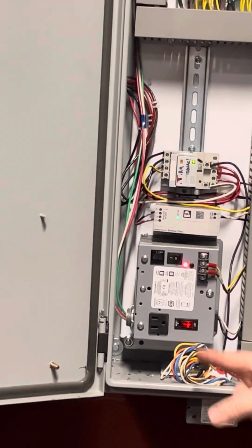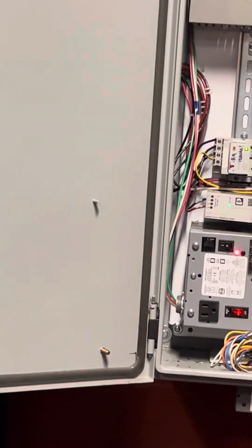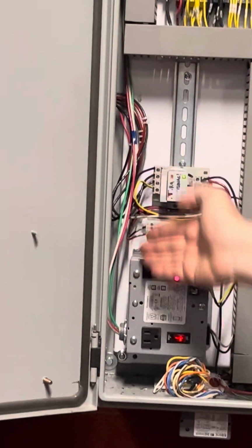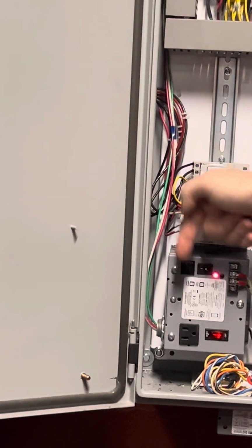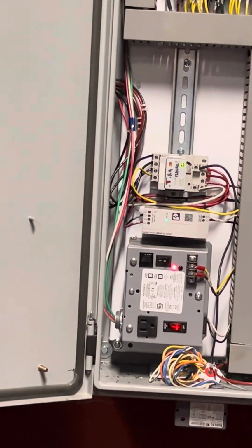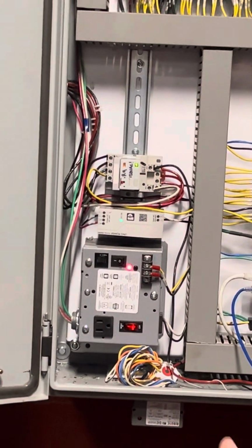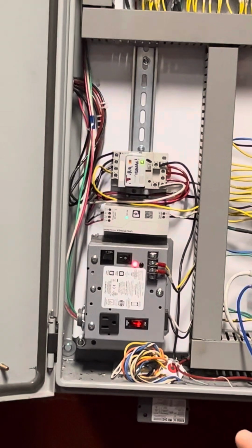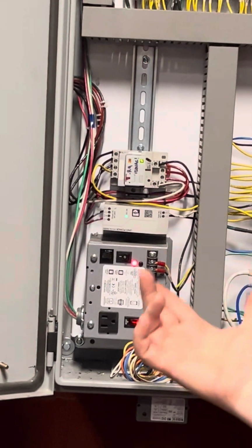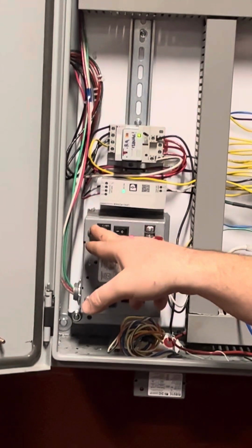Now, if you come into here, this light is red, but all of this is dark. Check this. This guy will pop out. It pops out this way, and it will show a big white area behind it. All you have to do is push that back in. If it's still continuing to trip, you need to call somebody out here to come troubleshoot this, because now we've got something where the 24 volts is shorted out and constantly causing that thing to trip. But it is completely resettable.